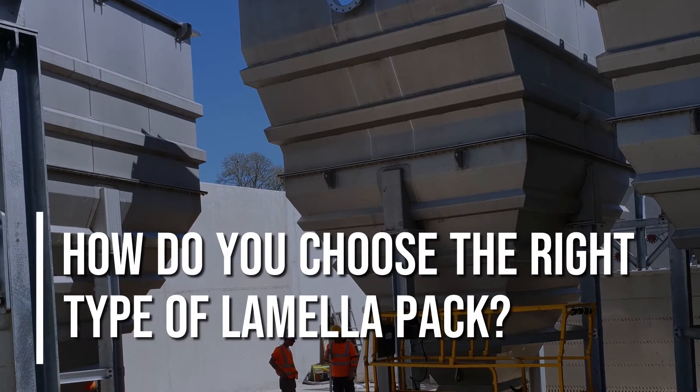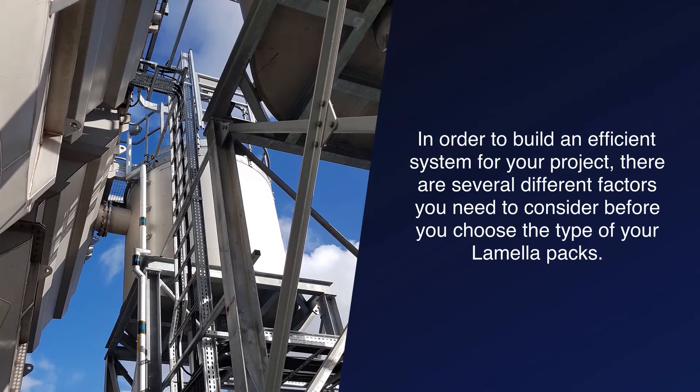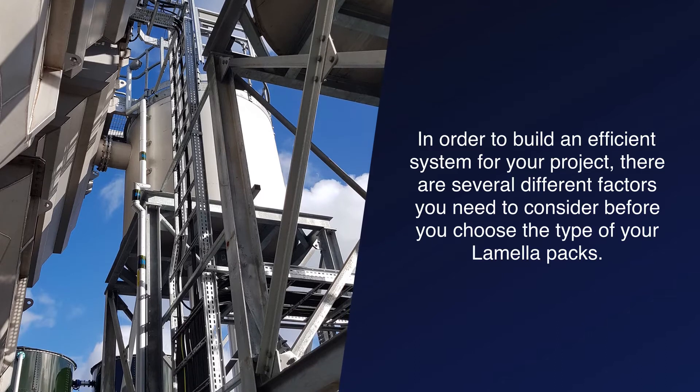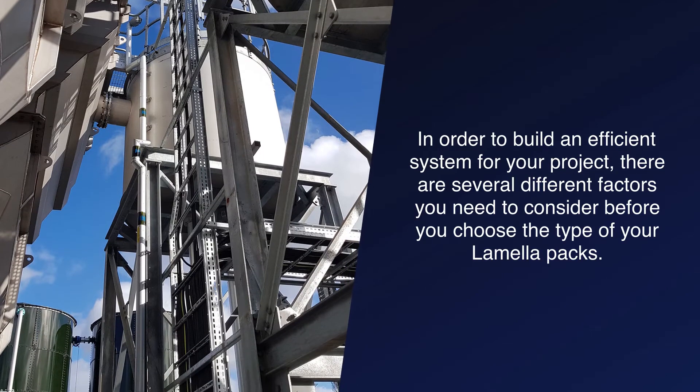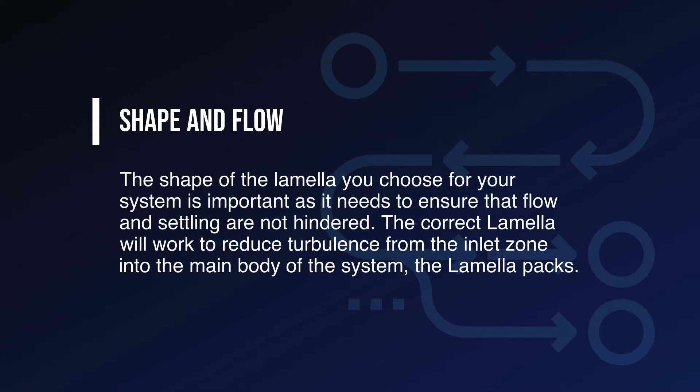How do you choose the right type of lamella pack? In order to build an efficient system for your project, there are several different factors you need to consider before you choose the type of your lamella packs. It is important to bear in mind that there are three possible types of lamella settling available: counter-current, cross current, and co-current. The shape of the lamella you choose is important as it needs to ensure that flow and settling are not hindered. The correct lamella will work to reduce turbulence from the inlet zone into the main body of the system, the lamella packs.